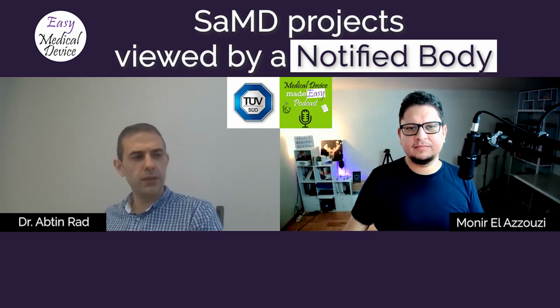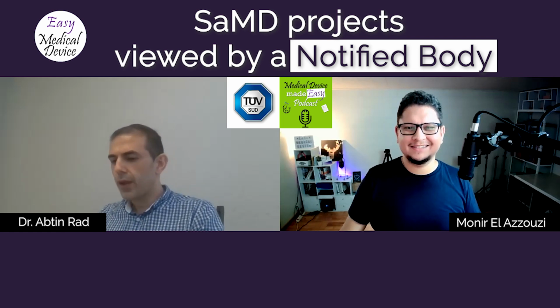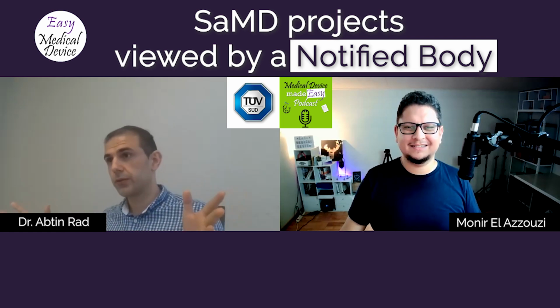And this MDCG guidance document is 2019-11, if I'm not wrong. They describe that there are actually three types of software. You have software that is incorporated or embedded in a medical device, and this software usually controls a medical device. So it does not have its own intended purpose. Those software usually are either covered by the device they are controlling and classified according to the medical device hardware, or as an accessory. And those are not covered as a medical device software.